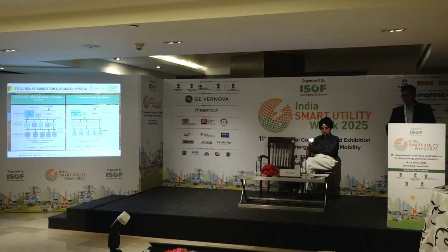So the fifth generation we are talking about is not much implemented, but many OEMs are working on it and implementing different POCs, and very successful POCs, where the protection and control device is virtualized. We are transferring this to some number of servers. Now, how many servers will be there? It depends on how the software is designed and developed, and on how big the substation is and what the data volume is. In this case, you can see we can use one redundant server; the server has to be IEC 61850-3 compliant, which is required for substation applications. With that, we can fulfill the complete requirement of the substation: the control and protection server as well as the gateway function can be accommodated, depending on the substation size, the data size and the criticality, and this would be a big advantage for us.